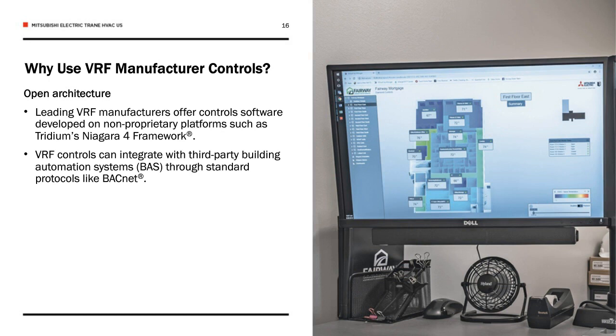The more complicated the piece of equipment, a large centrifugal chiller, a large air-cooled chiller, large boiler systems, those are going to have a lot more information, and we could make the graphics and the interface for the user as expansive or as simple as possible. I've seen several interfaces where there's just text. Is it on? Is it off? What's the set point? What's the threshold? What's the offset? And then I've seen systems where it's so complex as to completely visualize the entire unit.